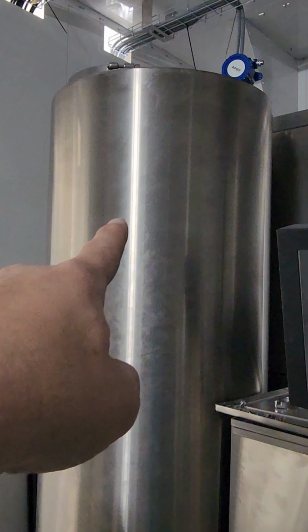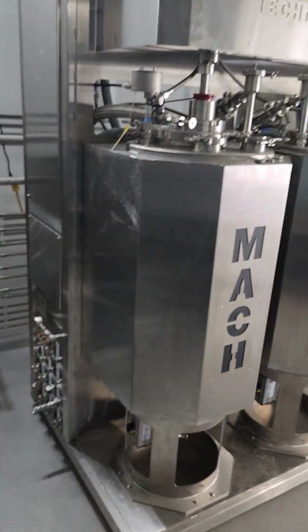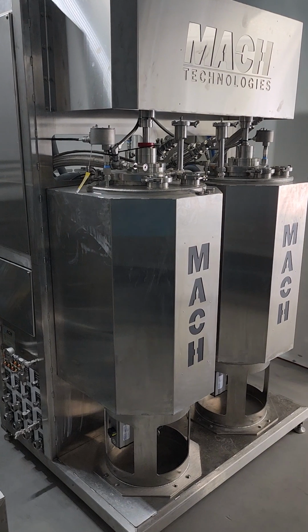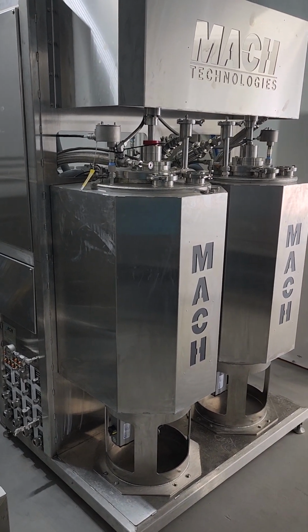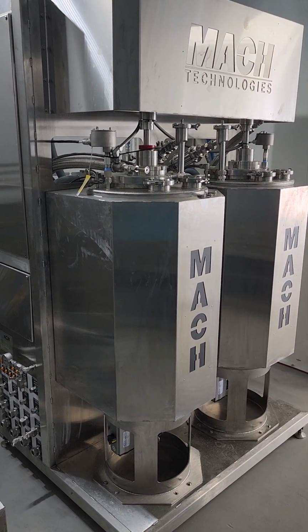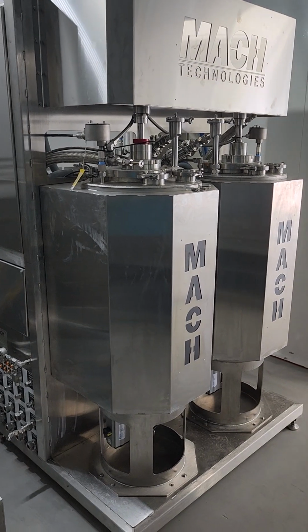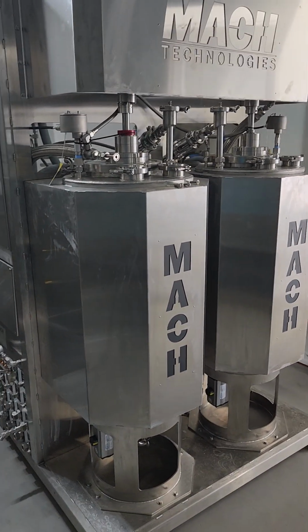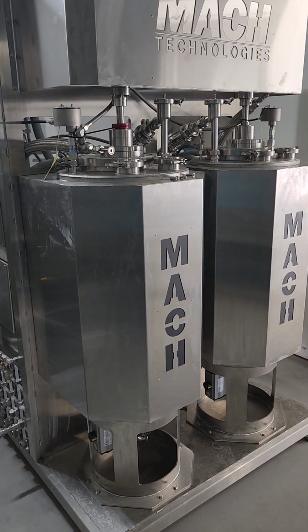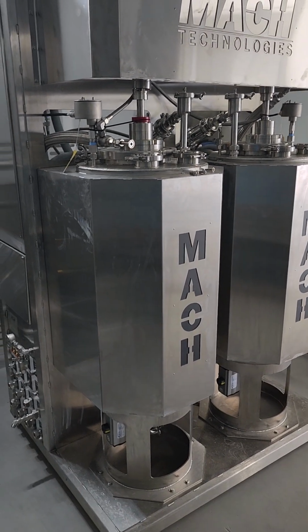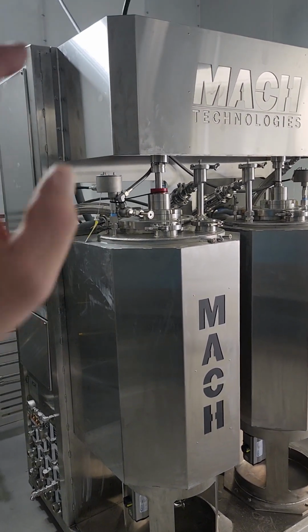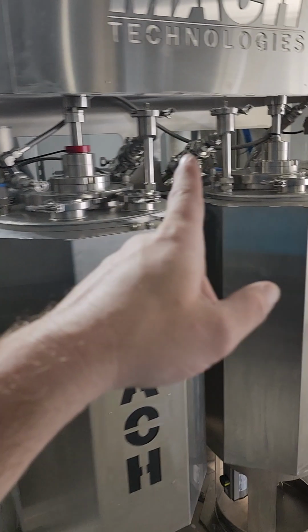You'd end up with both clean ethanol that gets recycled back to the holding tank at the front of the system, and your crude, which would get pumped over into our dual 100-liter decarb unit. It has some pretty cool technology with a stripping reactor to do a first pass, pulling off terpenes and some volatiles before it even hits the wipe film, so we're sending a cleaner oil out of our decarb unit.